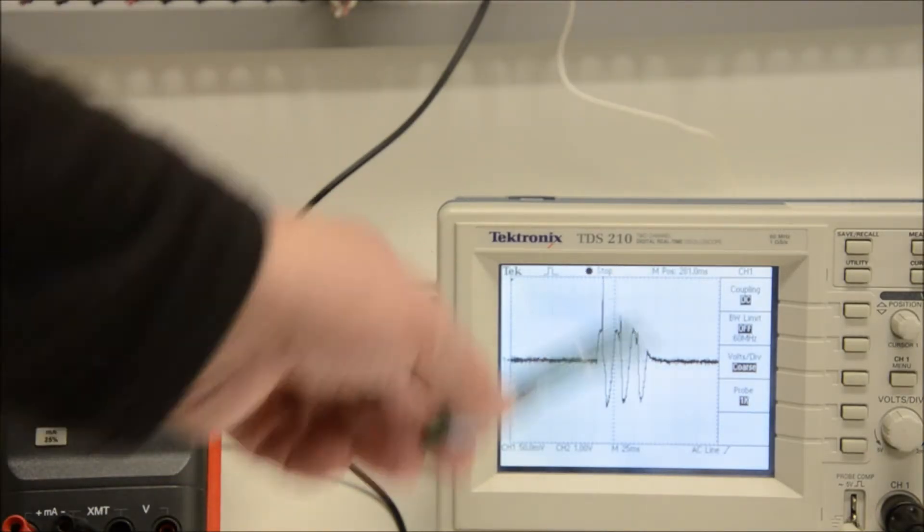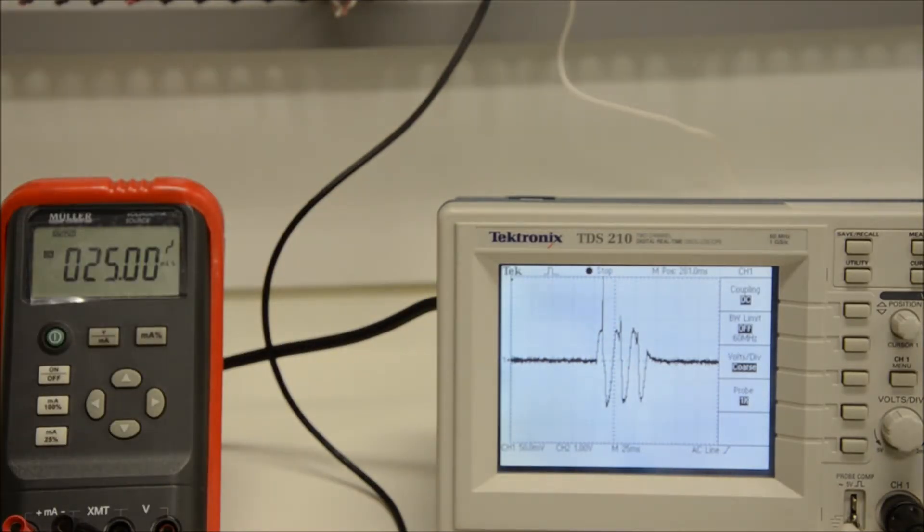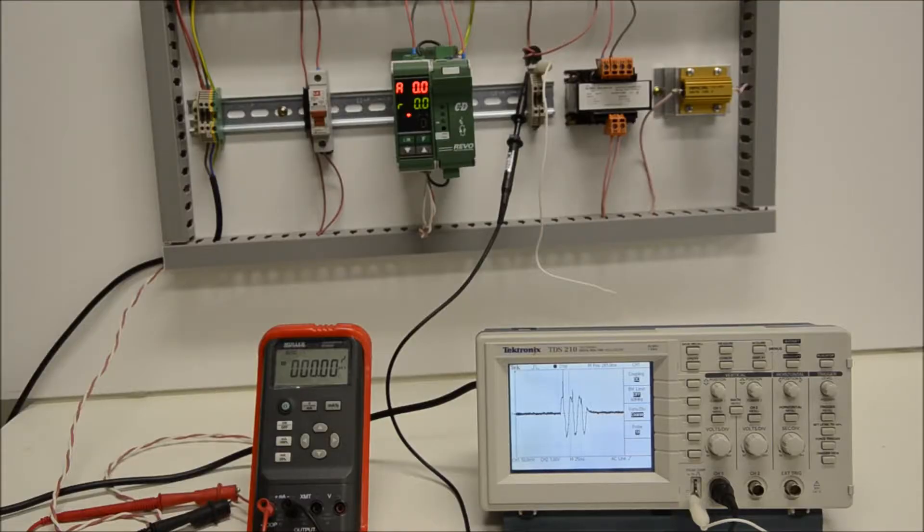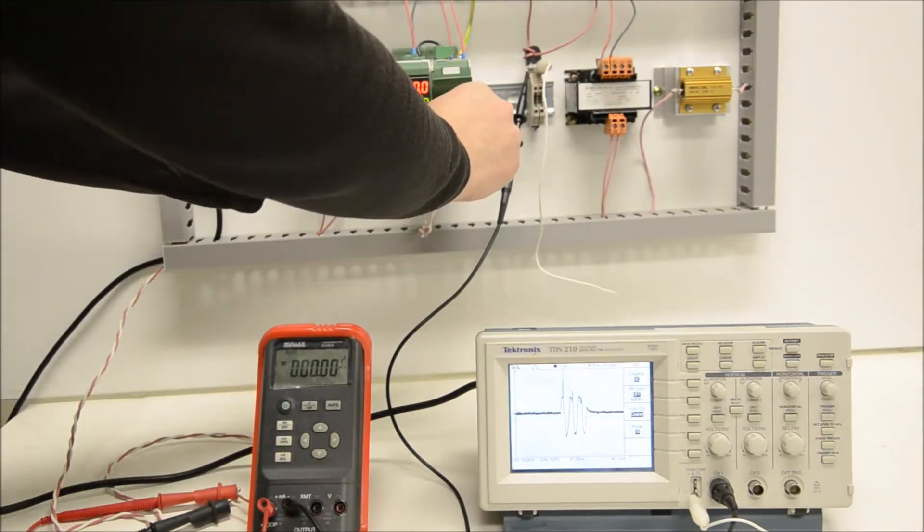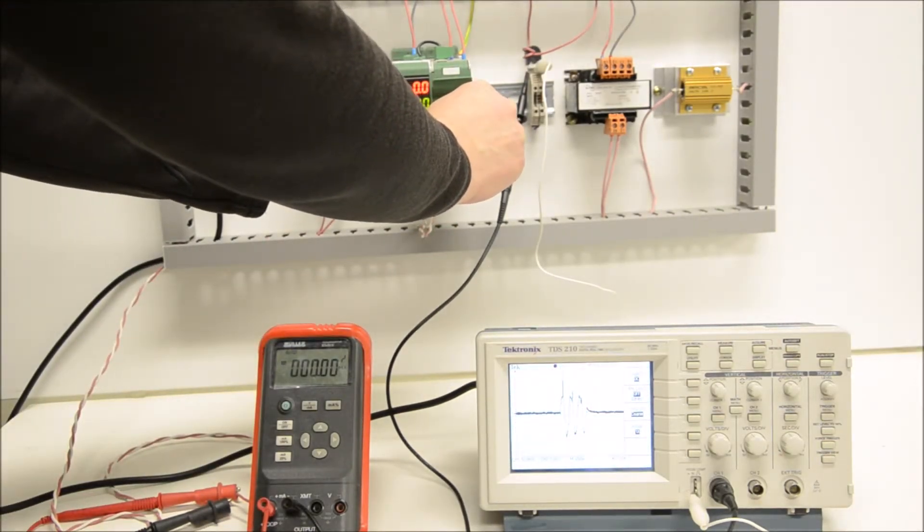In fact I can stop that. You can see that on the very first burst there's quite a high current coming through. That's due to transformer inductance. And the way that we can largely eliminate that and still burst fire is with delayed triggering.